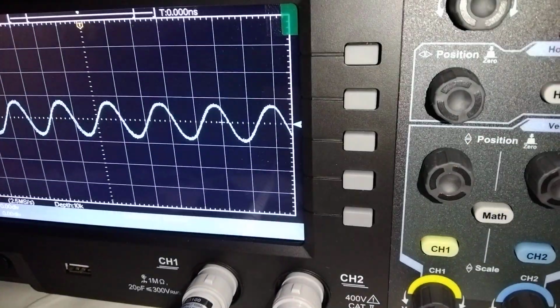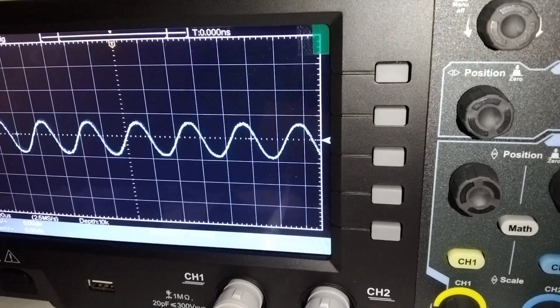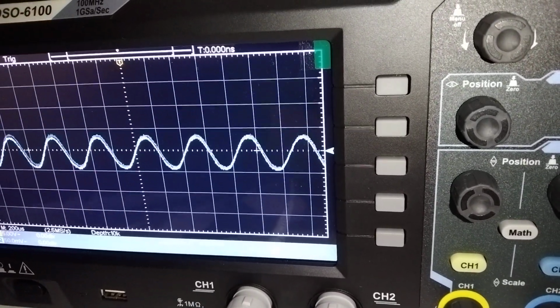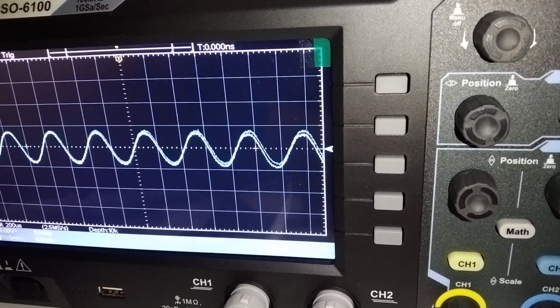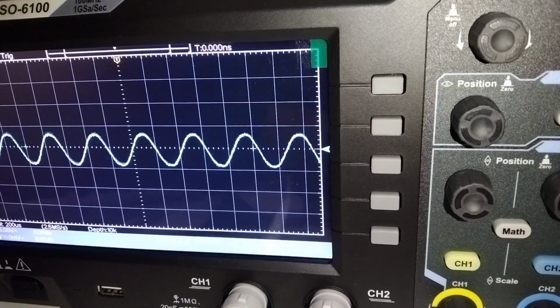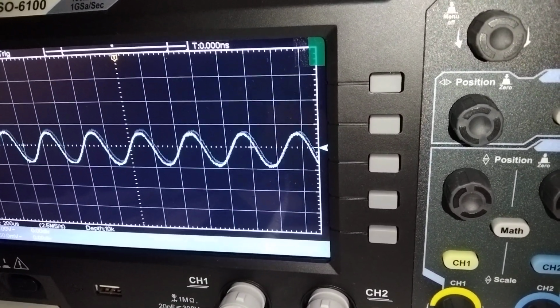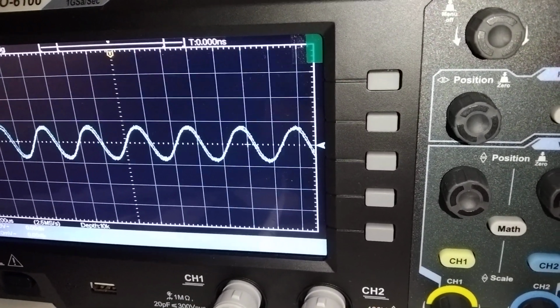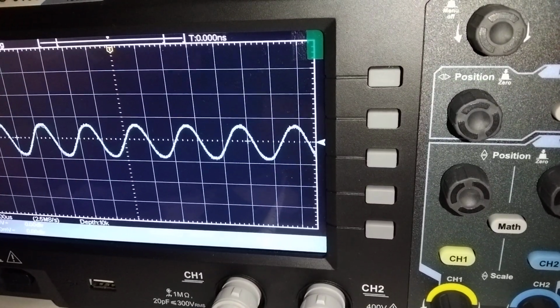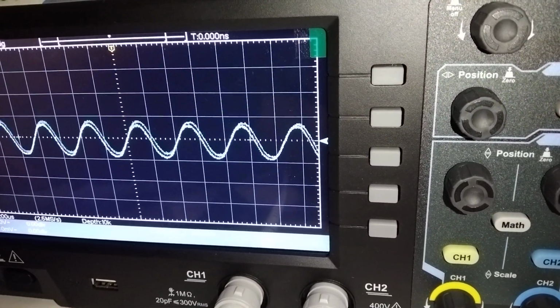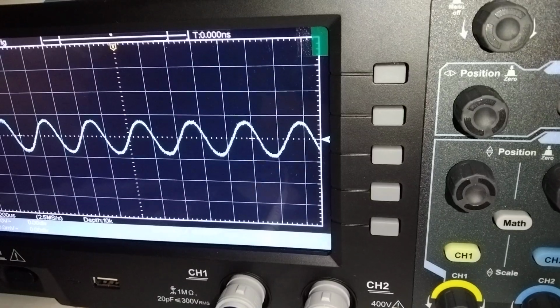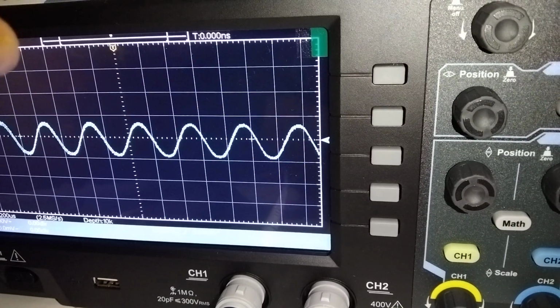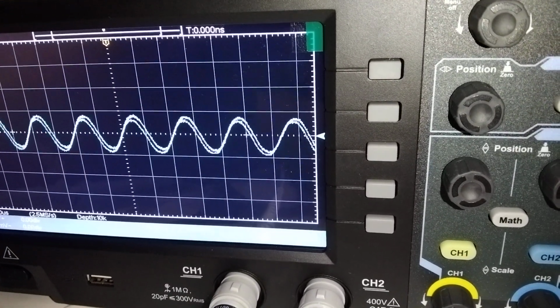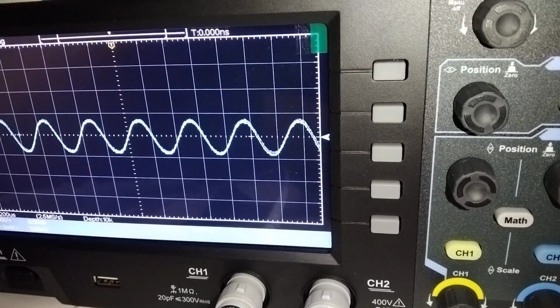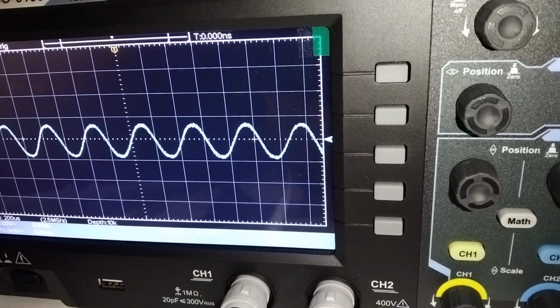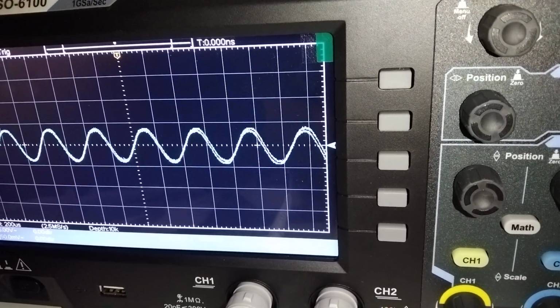must be run when you're using this DSO for a long time, and let's say your ambient temperature increases above 5 degrees Celsius. Now in that case you have to again self calibrate this DSO in order to ensure that it gives you the proper readings. Otherwise it is not required. So it is not desirable that you do self calibration frequently.